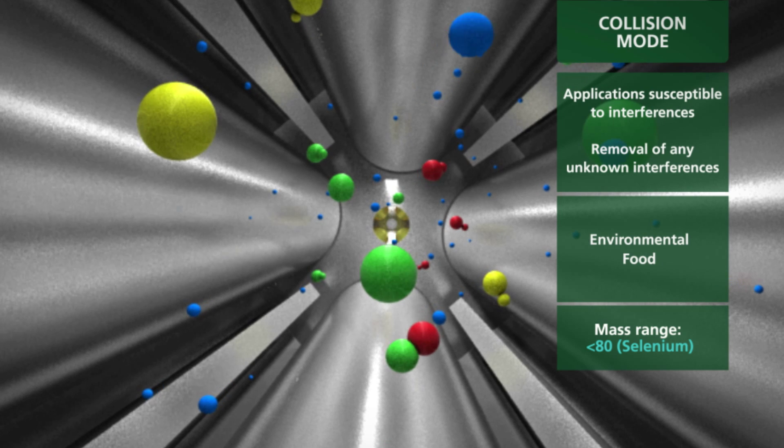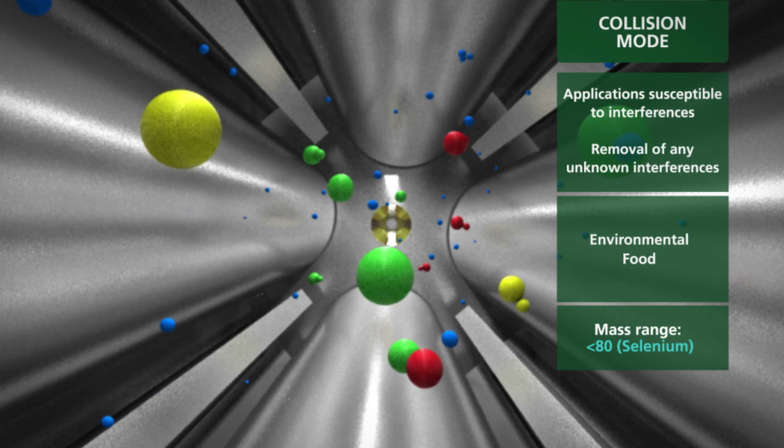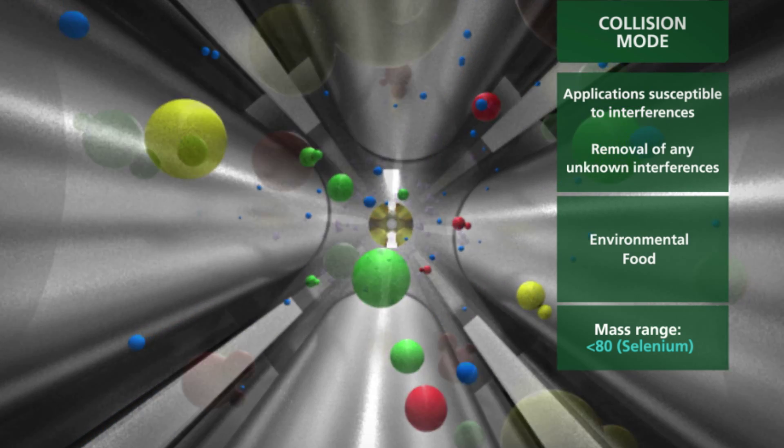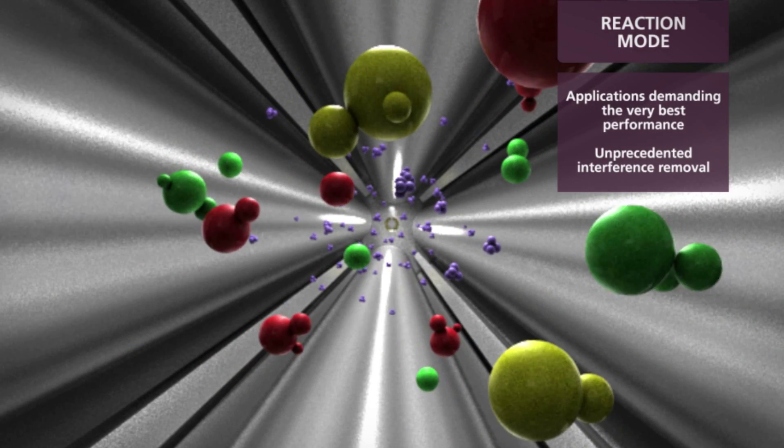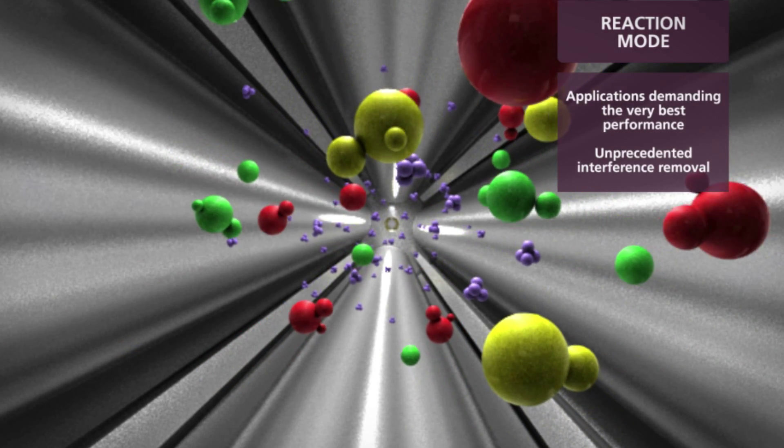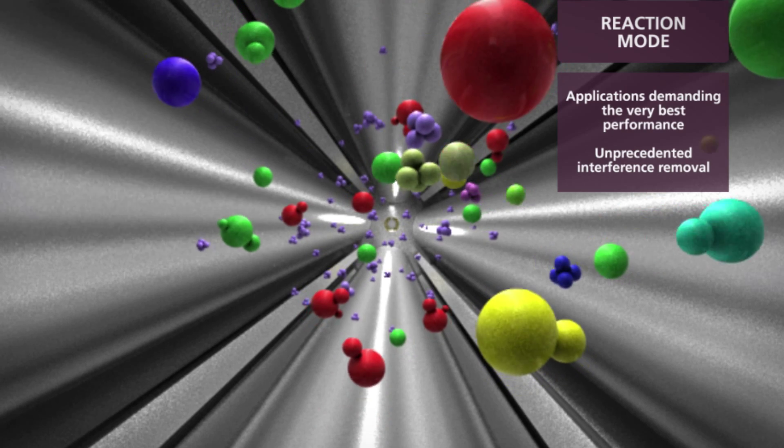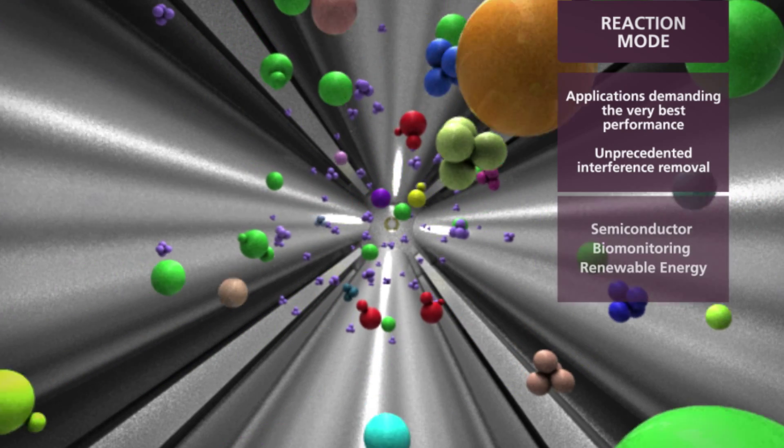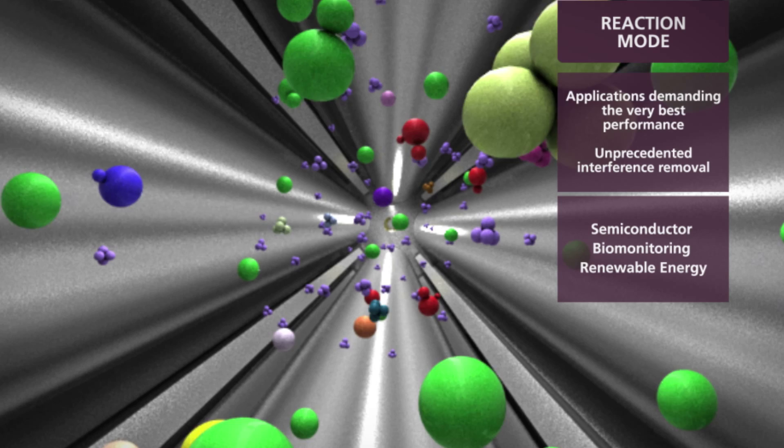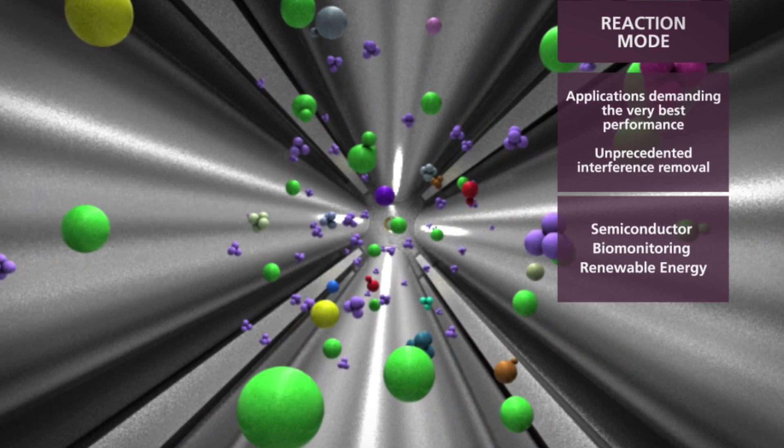If your analysis demands the very best performance and the greatest level of interference removal, there's no substitute for Nexion's reaction mode. Using controlled chemical reactions with any reactive gas, or gases, reaction mode removes the interferent with little or no loss of analyte sensitivity.